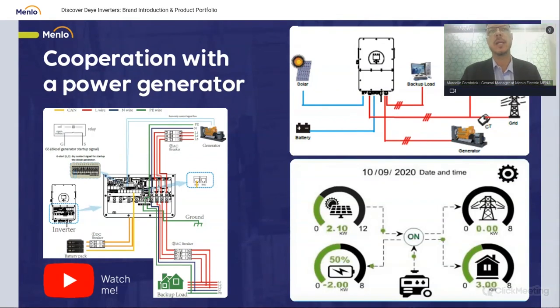Now, this is cooperation with a power generator. There's a power generator that connects to the generator port, and it makes the system very robust so that you will not run out of power. The control system from Deye will control the generator, when to start up and when to stop. You put your parameters in, and that would be your last source of energy. You put solar as your first priority, batteries as your second priority, grid as your third priority, and then the generator would be the fourth priority.